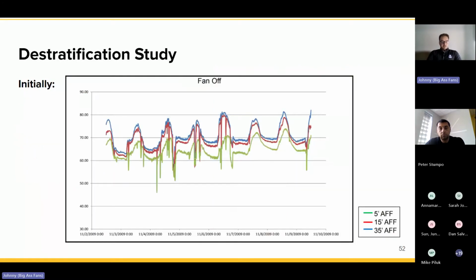When we installed those temperature sensors, we placed them at strategic heights: 5 feet being your thermostat height, 15 about midway up the space, and then 35 feet close to the roof deck. What you're seeing is about a week's worth of temperature data over time, and you can see the floor to ceiling difference is probably about 10 degrees Fahrenheit. Similar to what I mentioned off the hop, every foot of height is going to be some degree of stratification. We're seeing that here. The spikes are effectively your heating system kicking on and off to try and maintain that set point.